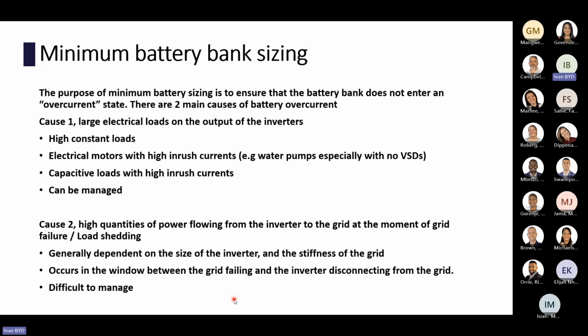And what happens is, when the grid dies, if you look at a very short time frame, your grid is at 120 volts 30 hertz or whatever, and your inverter is still trying to make its 230 volts 50 hertz, and the relay hasn't opened yet. In between the grid dying and the relay between the grid and the inverter opening, a lot of power flows out of the battery to the grid. So that's another reason why you need a minimum battery bank size to ensure that everything runs smoothly: the inverters can pull a lot of power from the batteries at that moment.